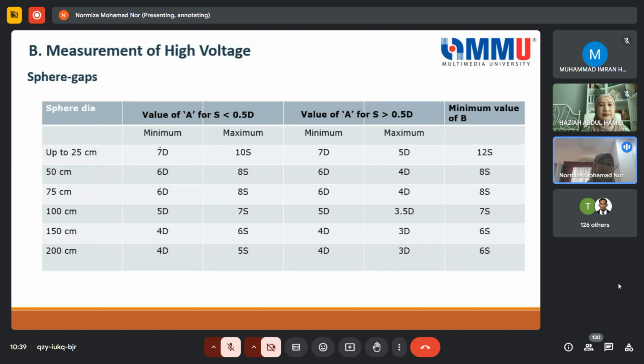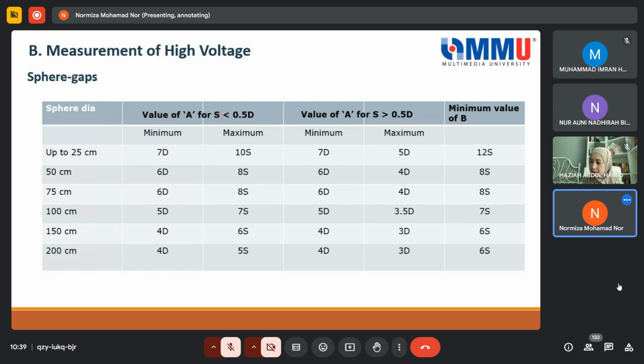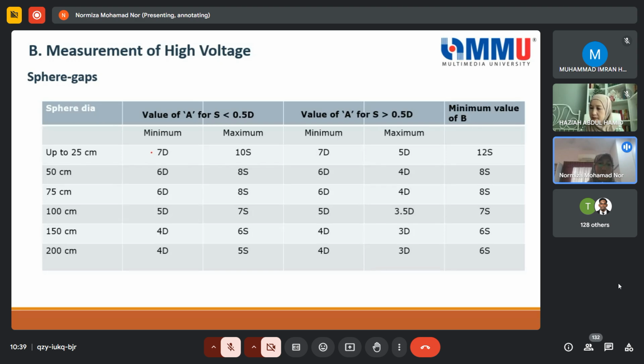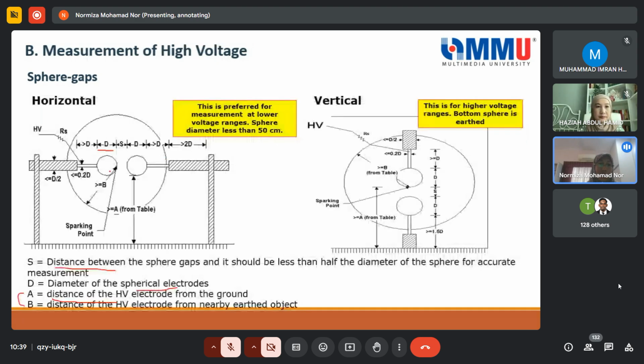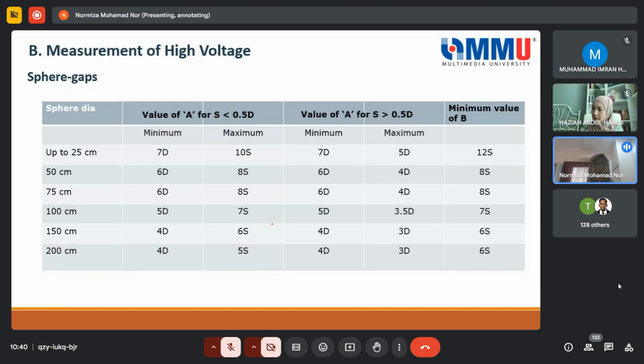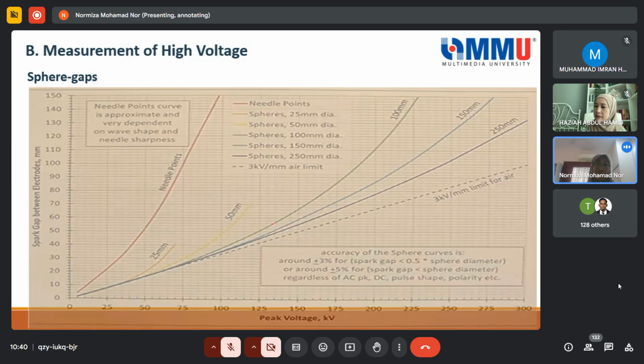Okay, this is the design. If you have 7D, the value of A for S less than 0.5 D, up to 25 cm for the diameter, then the minimum is 7D. You can see that the diameter here is actually defined already in this diagram. This is just to show that in the standard they give this guide that the high voltage lab engineer can consider.